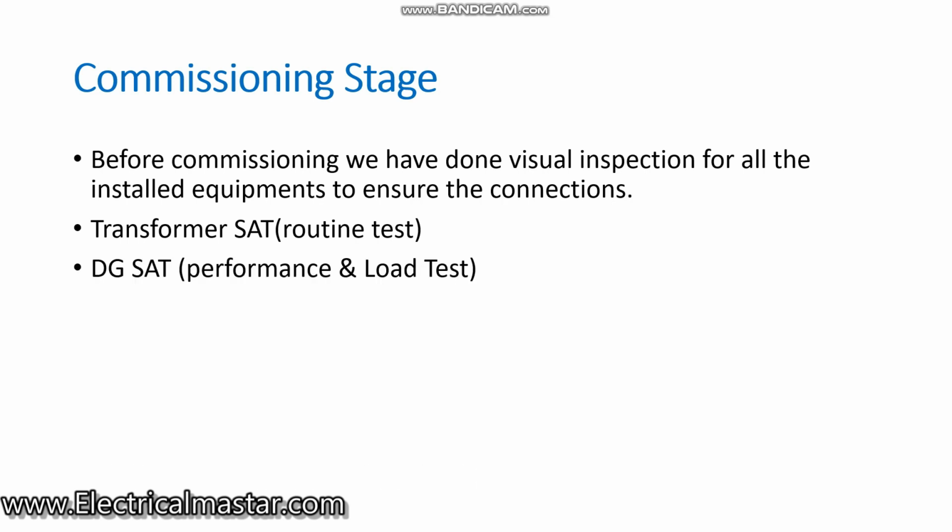I will give the link in the description. You can check it there. Then second, DG SAT. In the DG SAT I have done the performance test of the DG, the functional test of the DG, and also the load test.